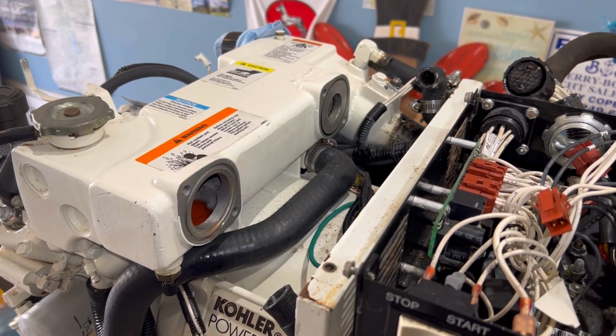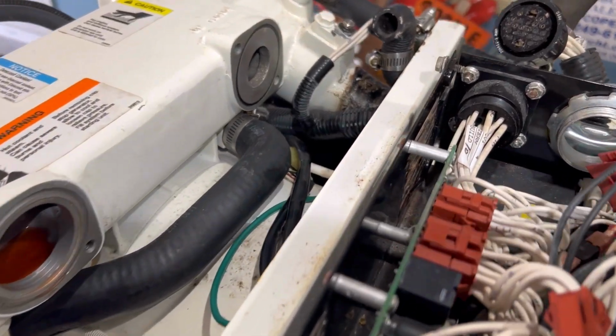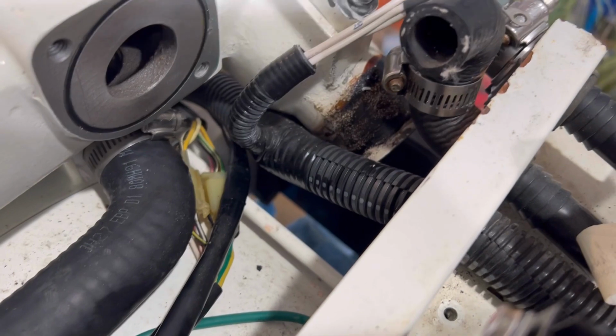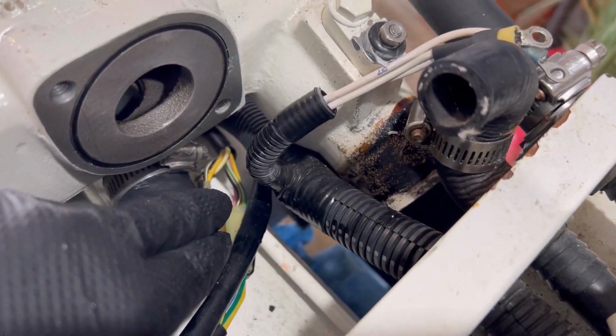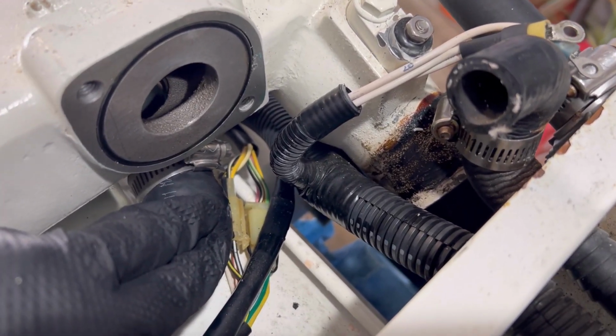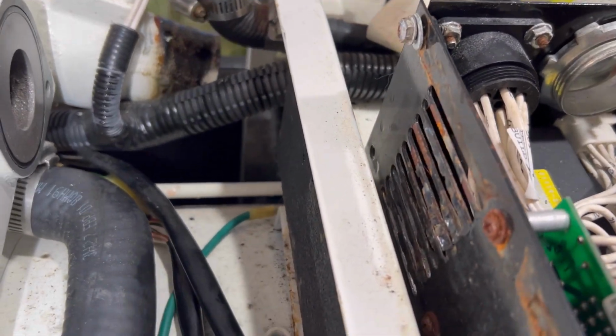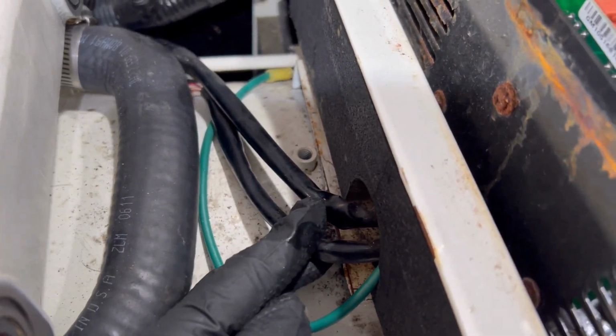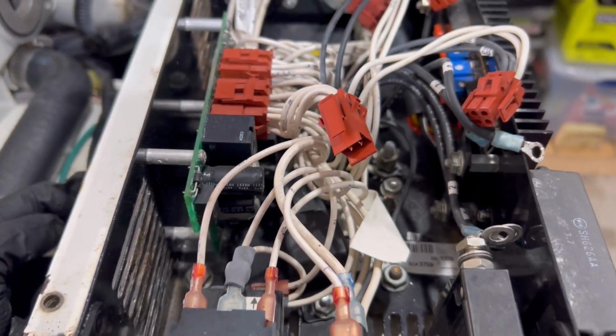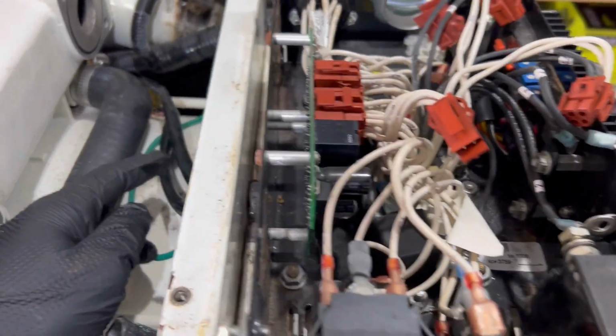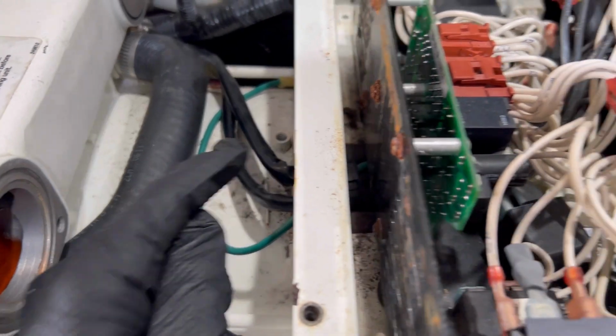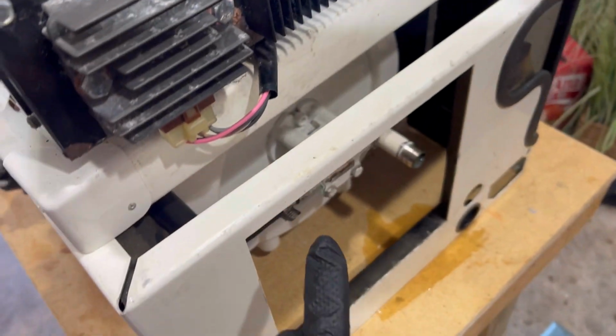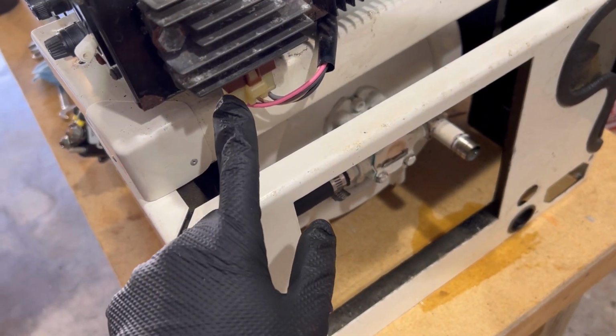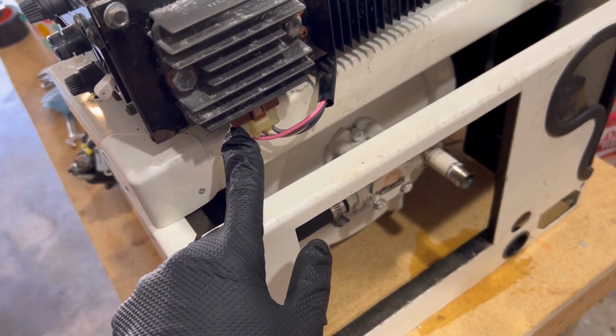With the heat exchanger removed, we now have much better access to disconnect these two off-white connectors here. These two feed into this bundle, which goes up inside the control box. The other one passes underneath and comes over to this connector, so I'm going to disconnect this.